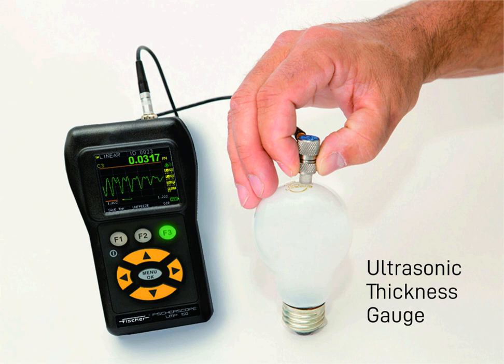Contact is usually assured by first removing visible corrosion scale and then applying petroleum jelly before pressing the probe against the metal. It is also used for monitoring pipelines.